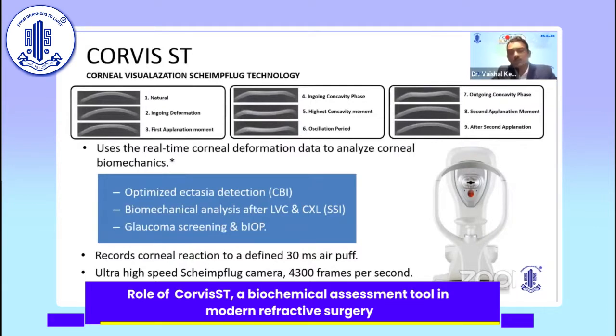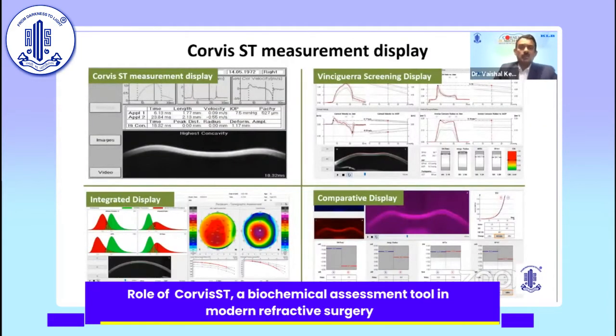The ultra-high-speed Scheimpflug camera uses 4,300 frames per second to record the deformation or corneal dynamic response. The Corvis ST is primarily used for optimizing ectasia detection, for biomechanical analysis pre- and post-LVC and cross-linking, for glaucoma screening, and it gives a BIOP or biomechanically corrected IOP. The Corvis ST essentially has the Vinciguerra screening display, the integrated display, and the comparative display.